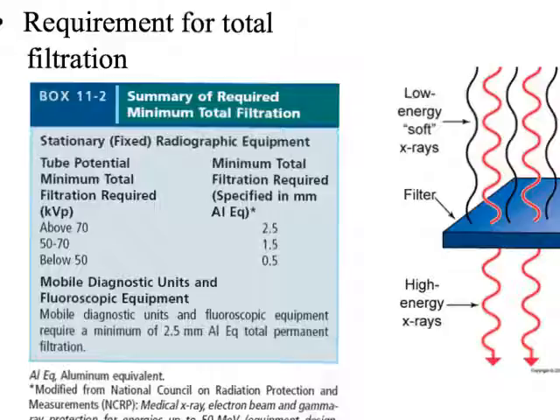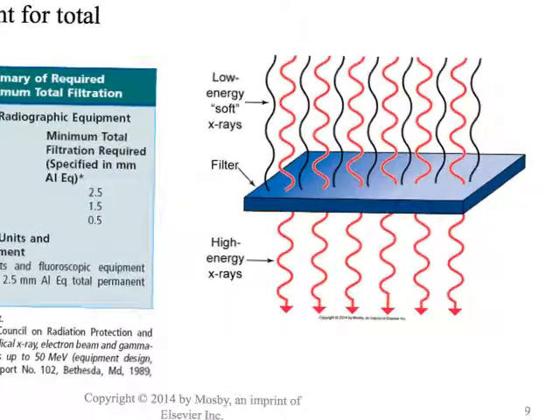This is related in part to the same thing that the radiation therapists are doing when they use compensating wedges. They're shaping the X-ray beam using a wedge, using some amount of aluminum equivalent to reduce the X-ray beam down to some shaped pattern. And there's a wide variety of those. But the big takeaway here is that what we're getting rid of is the soft X-rays, the low energy X-rays. So we're hardening the beam. We are reducing the quantity of X-rays that are exiting the tube, but we're increasing the overall quality. And so largely what we're doing is getting rid of those X-rays that would just contribute to patient's skin dose. So it is a way to reduce the patient's skin dose as well as occupational dose due to backscatter.